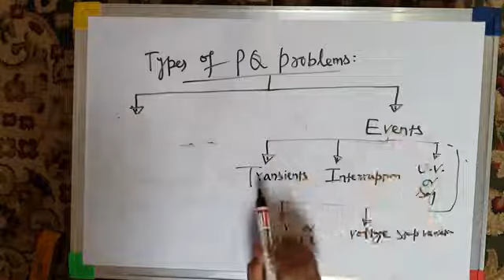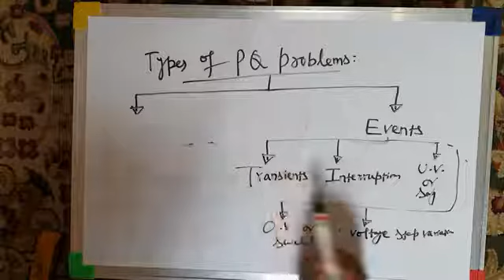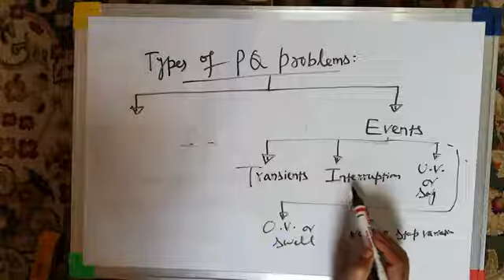Now, events may be broadly categorized as transients. Transients again may be of two types: impulsive transients and oscillatory transients. Then interruptions may be short interruptions or long interruptions. Then under voltage or voltage sag: if the dip in the voltage is for a very short period, it's called sag, and if it is for a slightly longer period, it's called under voltage. Similarly, there may be an increase in the voltage. The rise in the voltage is called swell. For short duration, if the voltage rises above its rated value, it's called voltage swell. And if the increase above its nominal value is for a slightly longer period, it's called over voltage. And then voltage step variation.